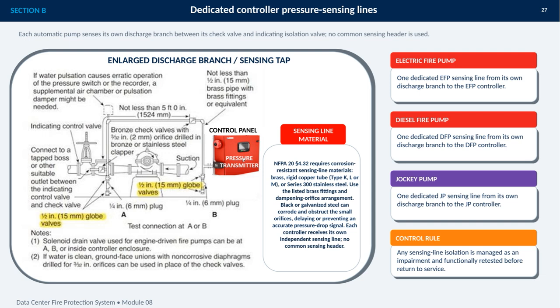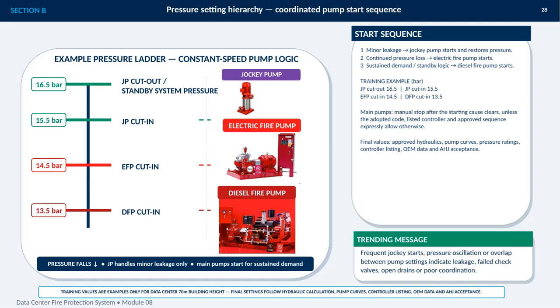returned to service. This slide illustrates a coordinated pressure ladder for constant speed fire pump logic. The purpose is to make each pump respond to a different level of pressure loss, rather than having multiple pumps start at once. The sequence begins with the jockey pump.